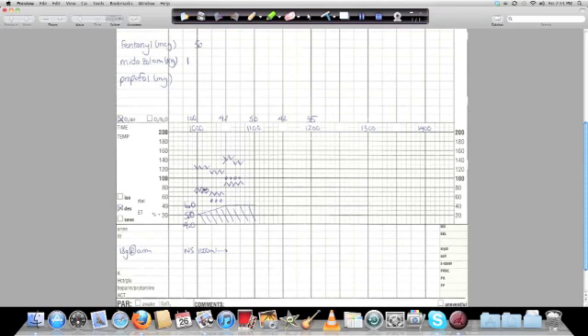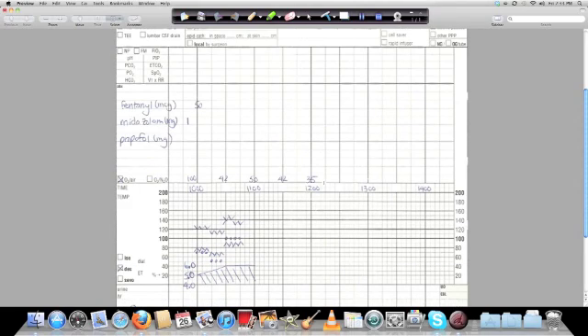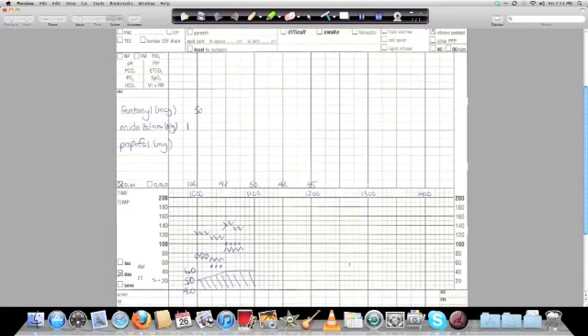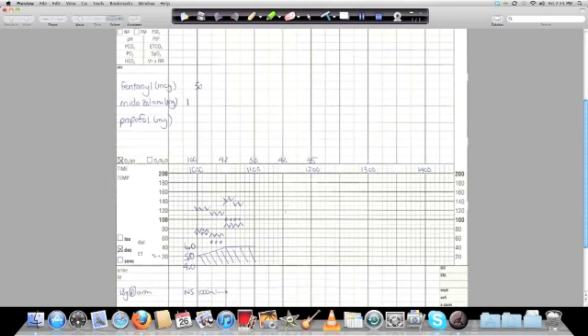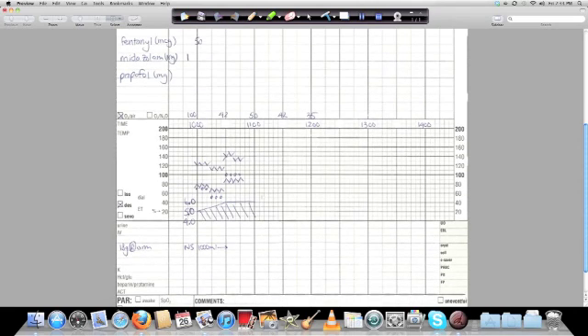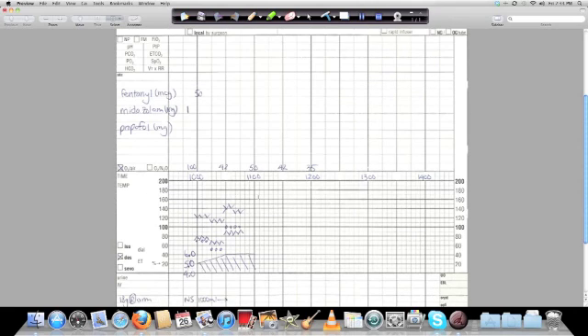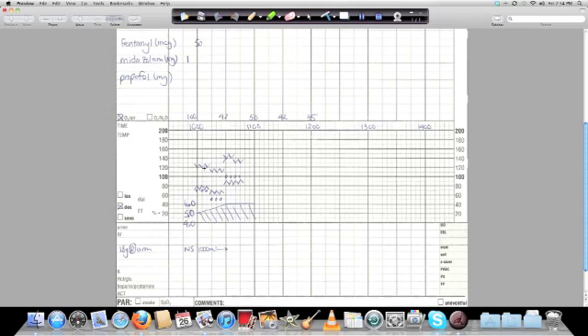And so, you track this throughout. Don't be concerned with making sure you check every five minutes. The machine itself, our friend Fabius GS here, will actually tabulate every five minutes the values for blood pressure and for heart rate and for pulse oximetry, which you would track up here. Once you get the operation underway, you can take a second, once everything's running smoothly, to jot down your notes. And that's usually the practice that's done in the operating room. Everything gets started. And then, you pull up the table on the anesthetic machine and tabulate everything as you go.